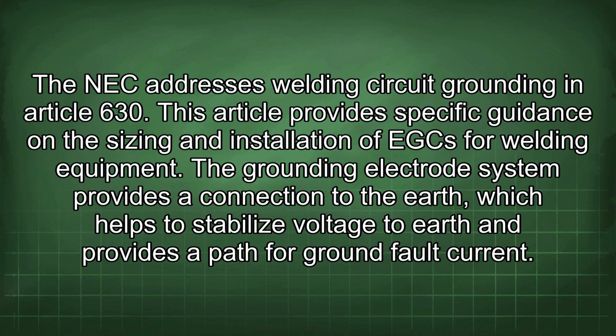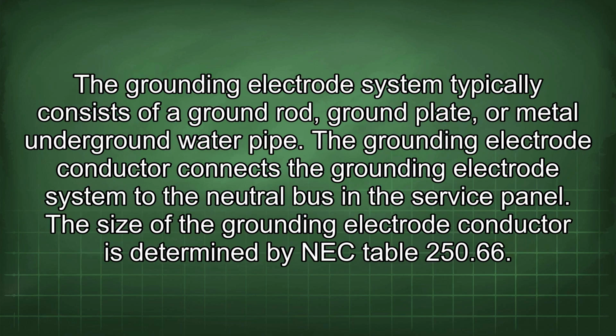The grounding electrode system provides a connection to the earth, which helps to stabilize voltage to earth and provide a path for ground fault current. The grounding electrode system typically consists of a ground rod, ground plate, or metal underground water pipe.